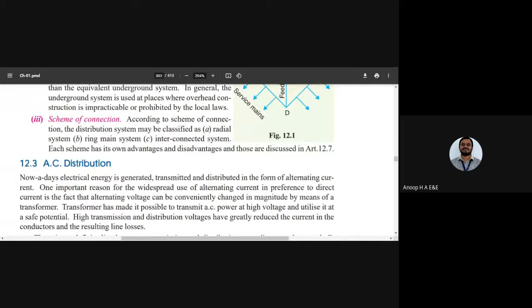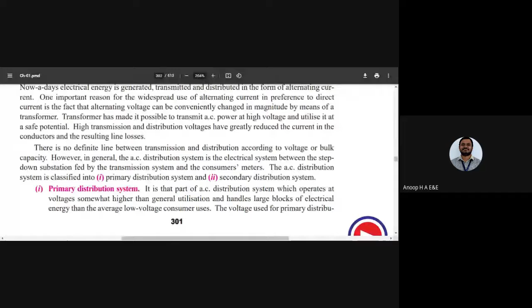Due to economic consideration, the primary distribution is carried out on a three-phase three-wire system. That is the reason why we want to have the three-phase three-wire system. There is no definite line between the transmission and the distribution according to the voltage or the bulk capacity. So again, it is divided into primary AC distribution and secondary AC distribution. That is the reason why in an electrical distribution system, you have the transmission side and the consumer meters which are connected after the secondary distribution.